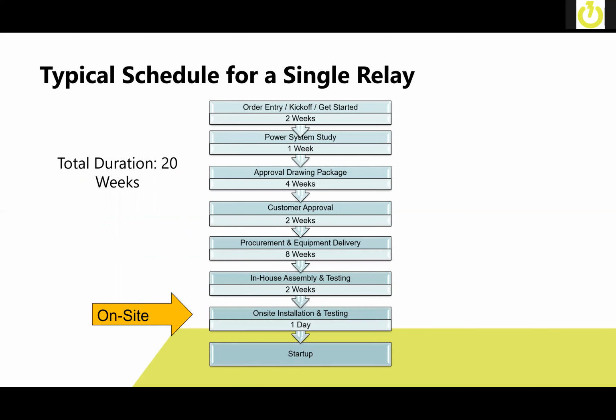So a typical schedule for a single relay, keeping in mind again that we're trying to do a power system study, full approval drawing package along with customer approval prior to doing equipment procurement and delivery. Typically we would see that from a total duration of 20 weeks. Again, this is for a single relay, more of an overcurrent feeder application. Depending on the complexity, it may increase some of this time or it may decrease some of it. Order entry, kickoff / getting started typically takes a couple of weeks, with a power system study following approximately 1 week afterwards.